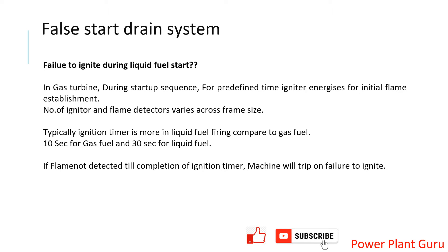In the gas turbine startup sequence, we understand there are certain numbers of igniters and flame detectors, which may differ for different machines. Once you start the process, there is introduction of fuel into the machine and then spark plugs ignite the fuel and air mixture. The ignition timer may be different for different fuels — 10 seconds for gas and 30 seconds for liquid fuel. If there is no sustainable or stable flame after this period, the machine does not detect that it is progressing on the startup sequence and will trip on failure to ignite.